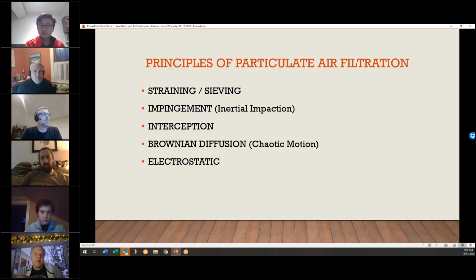Then there's also impingement, which basically means whatever's flying through the air smacks into the fibers of the filter and gets stuck. Usually the filter media will have some kind of sticky substance on them to help particles stick when they hit. Interception is where particles are just grazing the fiber of the filter, so they catch the edge of it. The particle is small enough to get through the filter, but as it goes through all those weaves, it's not going to make a clear shot, so it's going to hit something along the way. So that's basically what interception is.